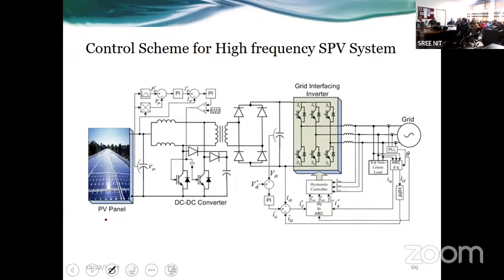It is just like a compact DC converter, and the inductance requirement will be lesser compared to a conventional buck boost converter. Gain is very high. In a normal buck boost converter, the gain from low voltage to high voltage DC is only 2 to 3 times. Here you can have n times. You can multiply. And plus, it is isolated from grid disturbance. Both the systems are isolated. So these are the advantages actually.